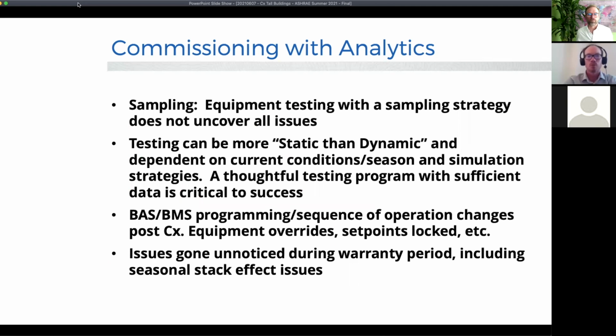So when we talk about this in a nutshell: sampling for a lot of the equipment, especially terminal units, we see a sampling strategy or a statistical sampling strategy, and that's fine, but that's the minimum. We understand we can't test every single VAV box or terminal unit in a tall building or most buildings, so having a sampling strategy historically has been the only thing we could do.